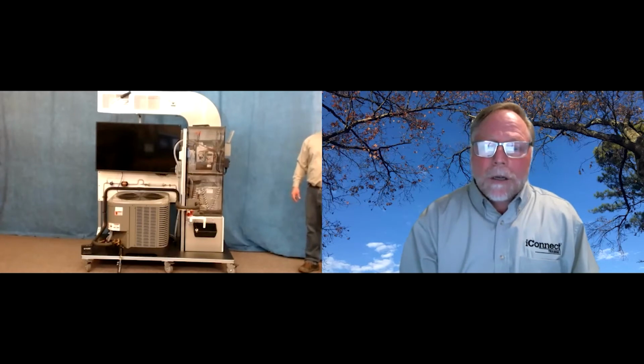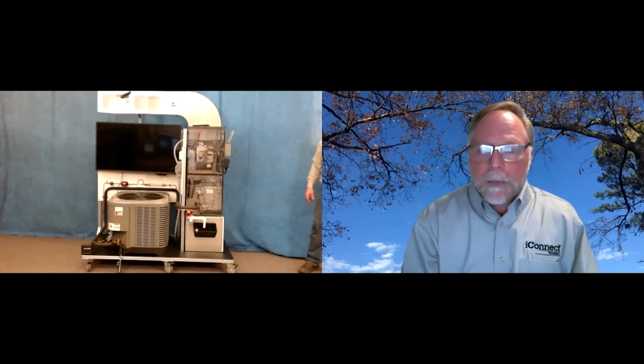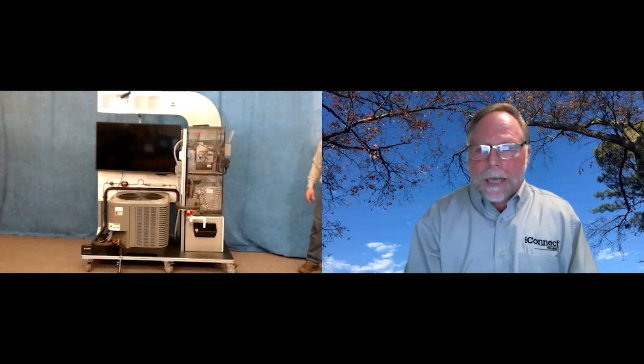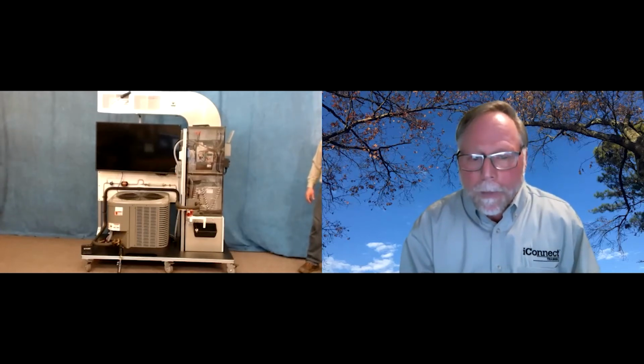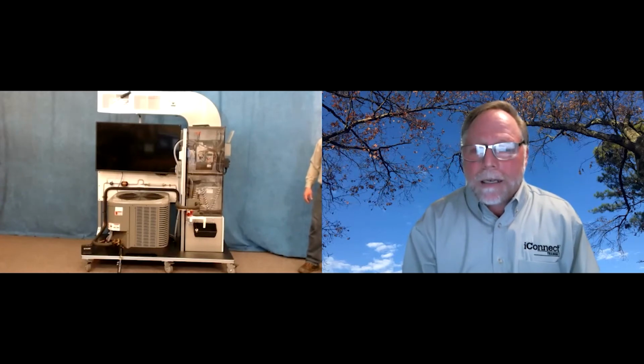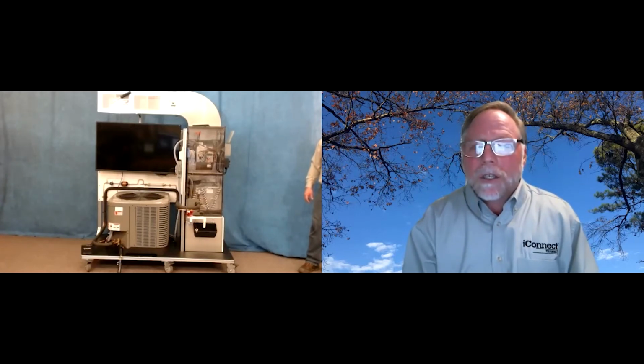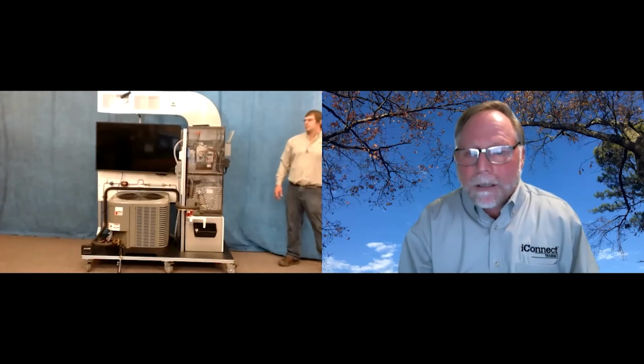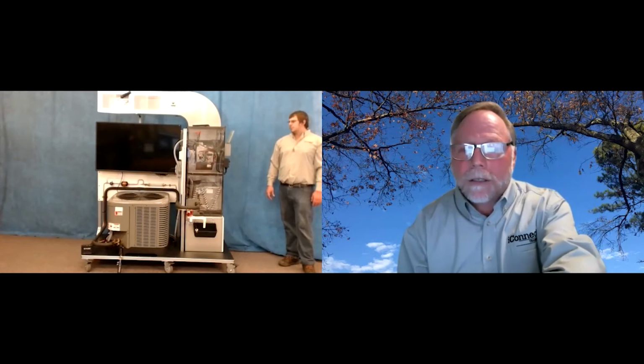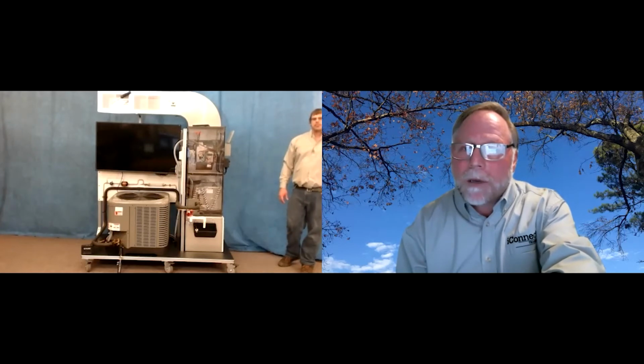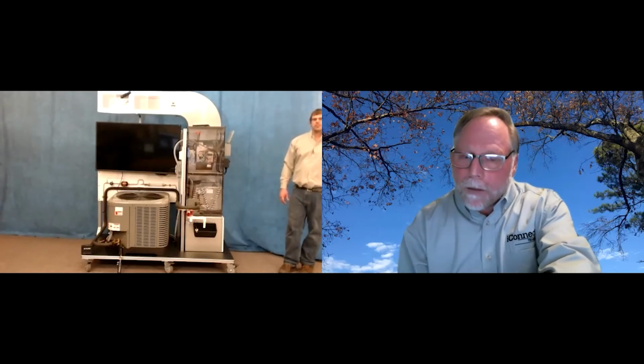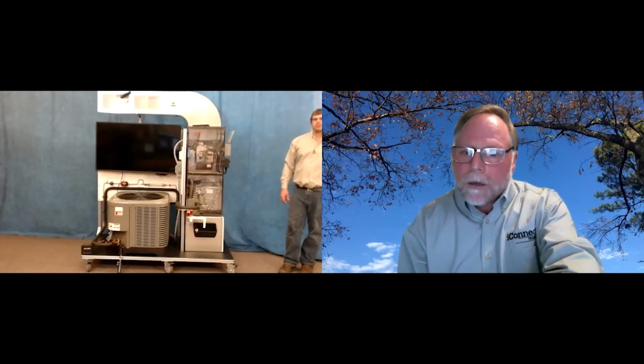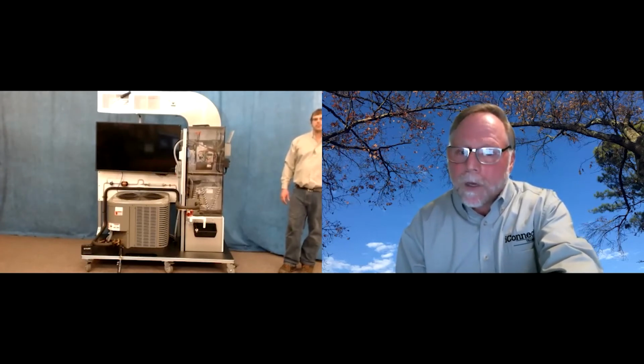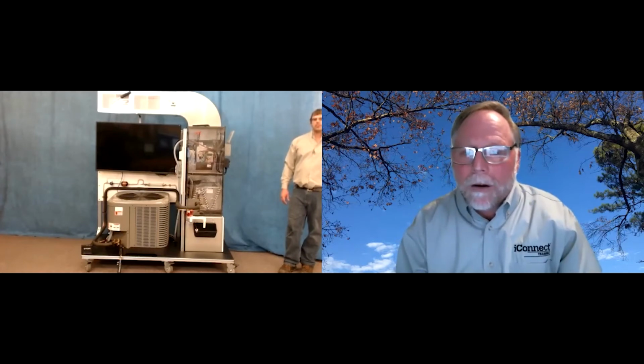Now keep your eyes on the suction pressure and temperature, and then also at the same time the superheat. The suction pressure is immediately dropping because it's no longer absorbing heat out of the air. This is what a dirty filter does to your unit. Now, if you look down the superheat, it's staying fairly constant because the expansion valve is doing its job. The expansion valve is maintaining superheat, but the more the system runs with that dirty filter, we're getting close to freezing. So we're at a 37-degree evaporator coil right now.